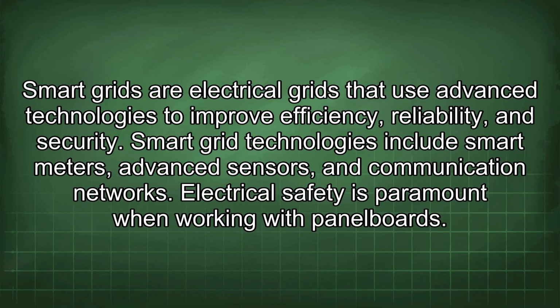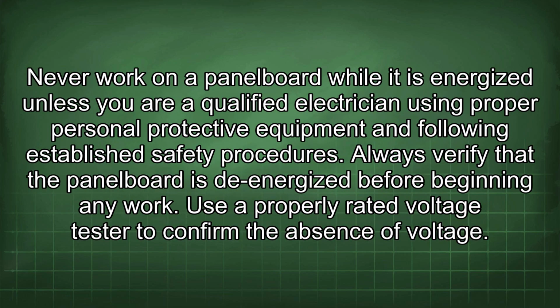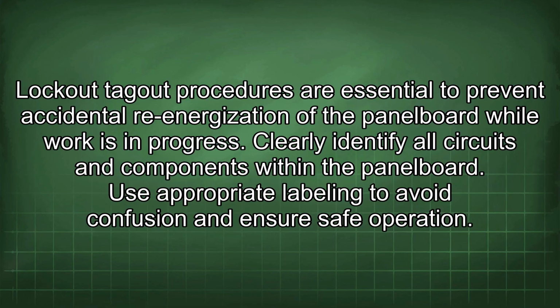Electrical safety is paramount when working with panelboards. Never work on a panelboard while it is energized unless you are a qualified electrician using proper personal protective equipment and following established safety procedures. Always verify that the panelboard is de-energized before beginning any work. Use a properly rated voltage tester to confirm the absence of voltage. Lockout-tagout procedures are essential to prevent accidental re-energization of the panelboard while work is in progress.